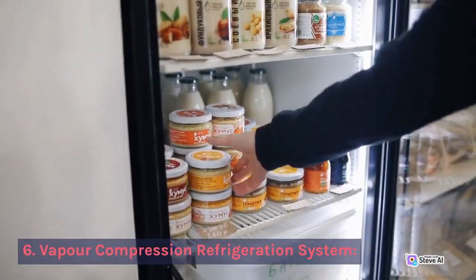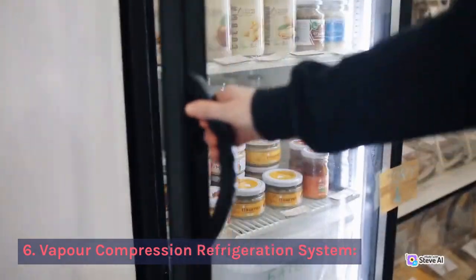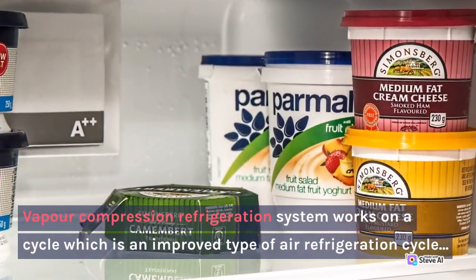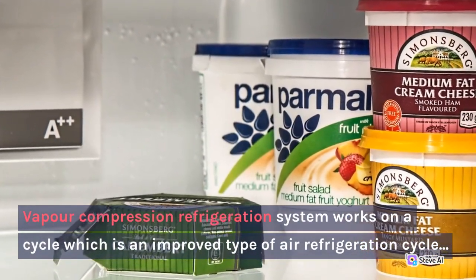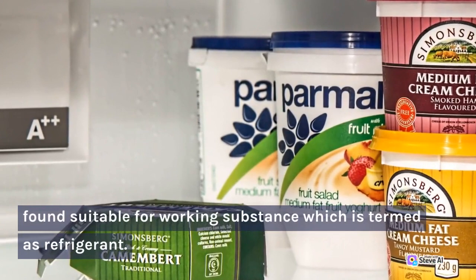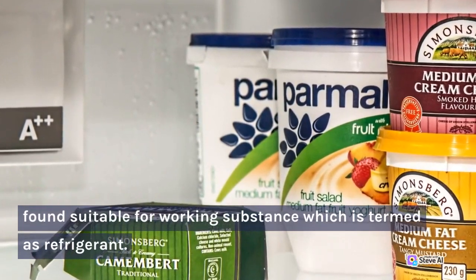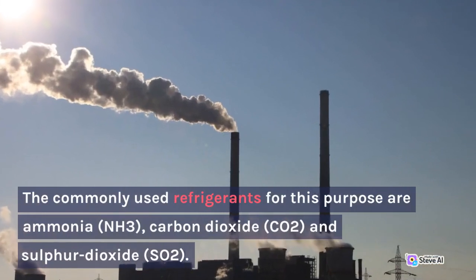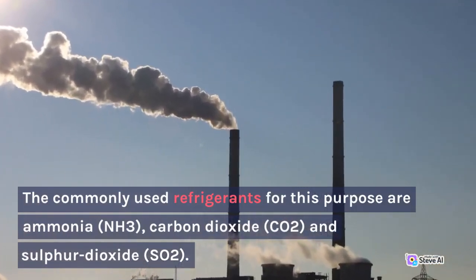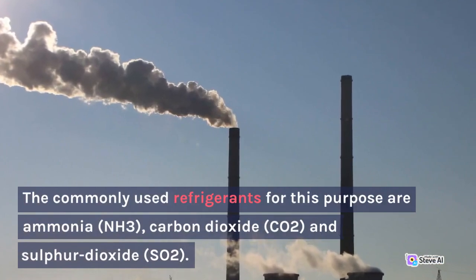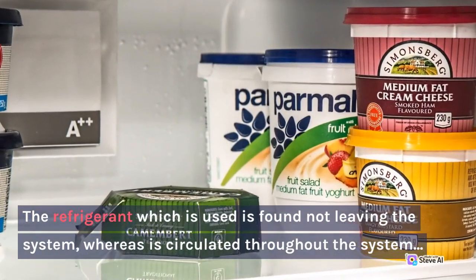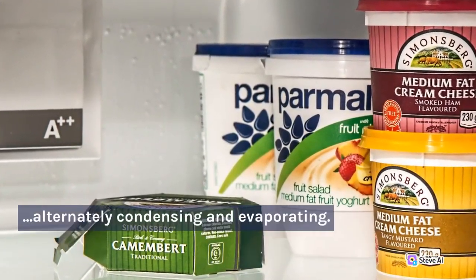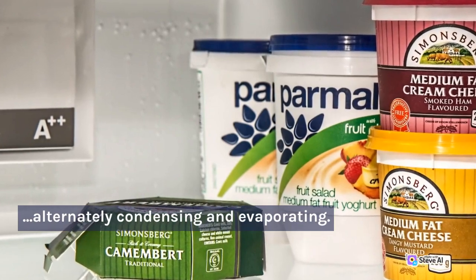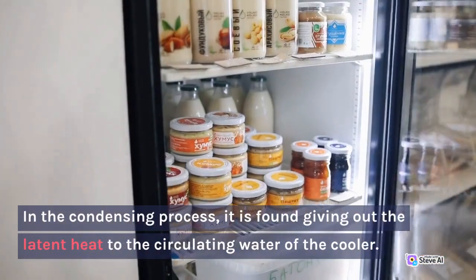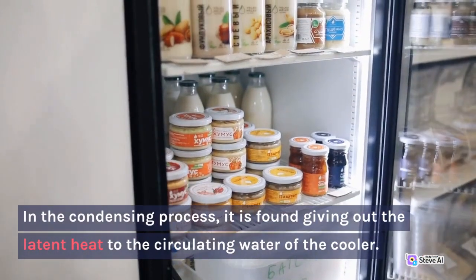6. Vapor compression refrigeration system. The vapor compression refrigeration system works on a cycle which is an improved type of air refrigeration cycle, suitable for a working substance which is termed the refrigerant. The commonly used refrigerants for this purpose are ammonia, NH3, carbon dioxide, CO2, and sulfur dioxide, SO2. The refrigerant does not leave the system but is circulated throughout it, alternately condensing and evaporating. In the condensing process, it gives out latent heat to the circulating water of the cooler.